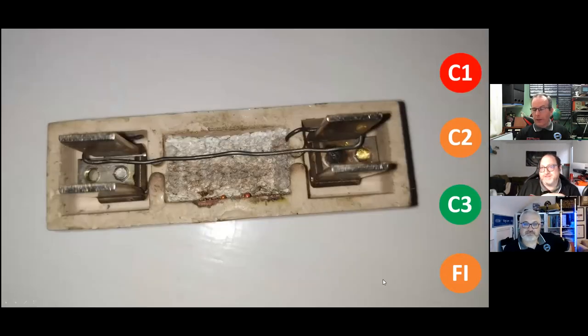The front cover's not there because it's obviously cutting off. Right, this one is a fuse, obviously. It's a rewirable fuse, and this is how it was taken out. And there's some bits missing from this, which is why the wire has been twisted round in that fashion, because there should be a screw at each end that the wire actually goes round. Is that a staple? Is that a paper clip? It is actually fuse wire. It's probably the wrong size. It looks almost like someone's managed to lodge a paper clip round it. But the fixing screws, the one on the left is just missing, and the one on the right has actually sheared off.